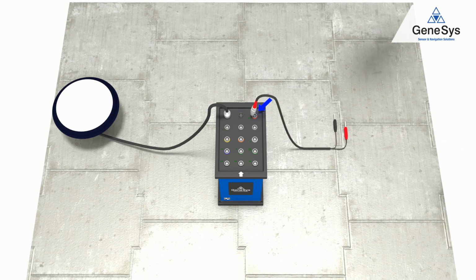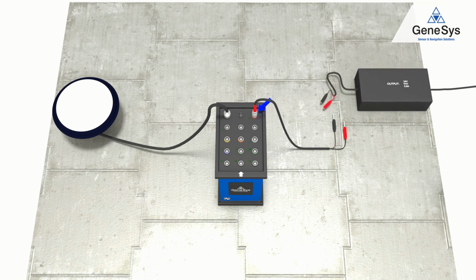The DC in connector needs a power input of 9 to 32 volt DC. If power is connected, the first LED turns on, and after the system has booted, the second LED gets powered. The ADMA is ready for operation now. The power consumption depends on the system, but never increases above 25 watts.